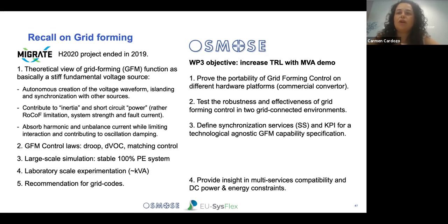Then we had laboratory scale experimentation and ended up with some recommendations for grid code. But somehow we were trapped in the discussion of what the technology is really able to do - whether this can be equivalent to a synchronous condenser, for instance, to cope with the scarcities Sheila just presented regarding inertia or voltage regulation. So in OSMOSE, we tried to engage this discussion with manufacturers and academia to end this loop of what the technology is capable of doing, and the other question - what does the system need?